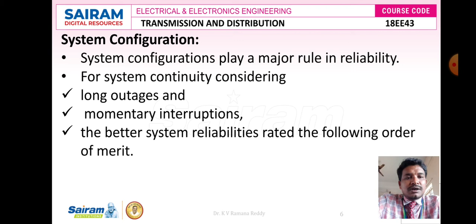Better system reliability is rated in the following order of merit: grid network, spot network, secondary selective, primary loop, and radial. So whenever we have a grid network, we then look at the spot network. Within that spot network, we select either a secondary selective system or a primary selective system. Then we look at the primary loop and radial loop, thereby providing continuity of electrical power supply even when a fault has taken place.